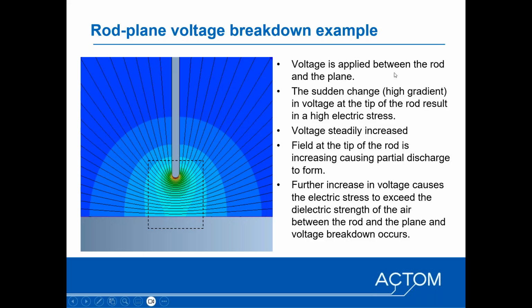Now I have a video that I can quickly show of the phenomena in terms of the voltage breakdown. The setup is that we have the rod at the top and the plane at the bottom, and when the voltage is applied, you have the discharge happening on the actual electrode. As the voltage gets increased, more corona will form, more partial discharge will form, up to the point where the medium between the electrodes cannot withstand it anymore, and a physical breakdown will happen. So that's effectively the mechanism for breakdown due to high field stress.